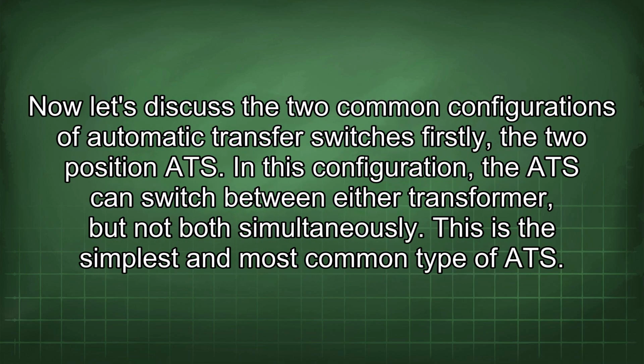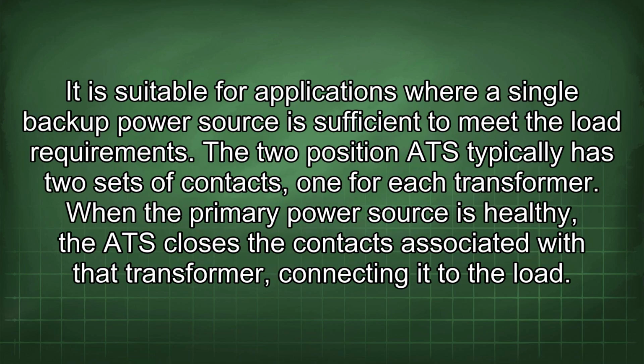Now let's discuss the two common configurations of automatic transfer switches. Firstly, the two-position ATS. In this configuration, the ATS can switch between either transformer, but not both simultaneously. This is the simplest and most common type of ATS. It is suitable for applications where a single backup power source is sufficient to meet the load requirements.